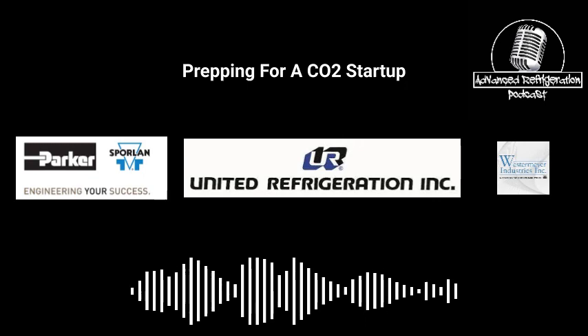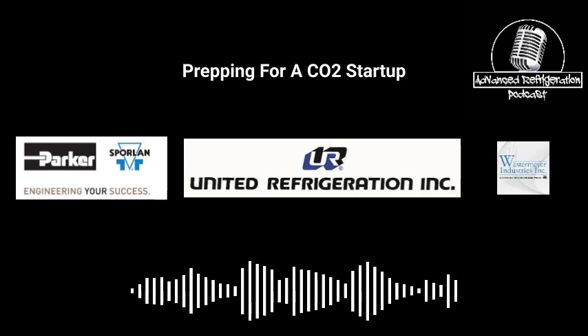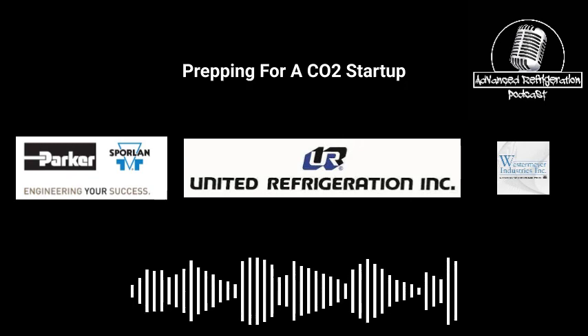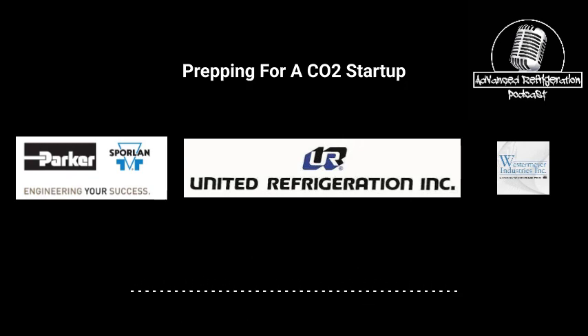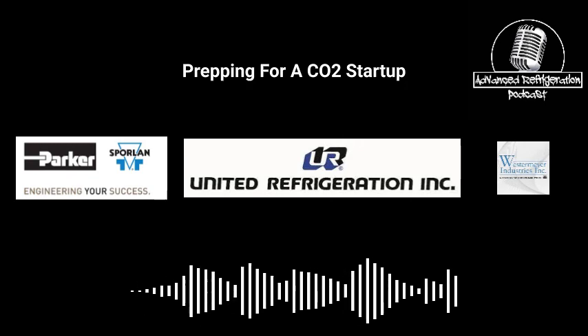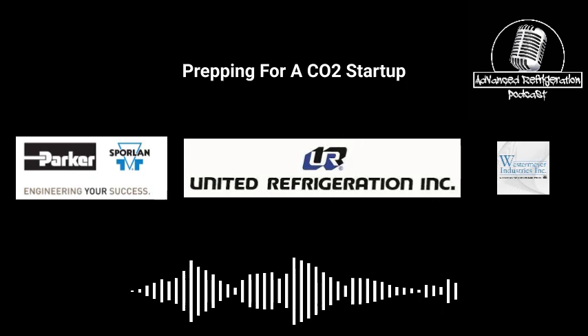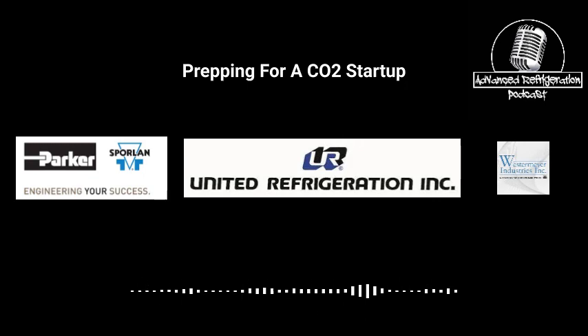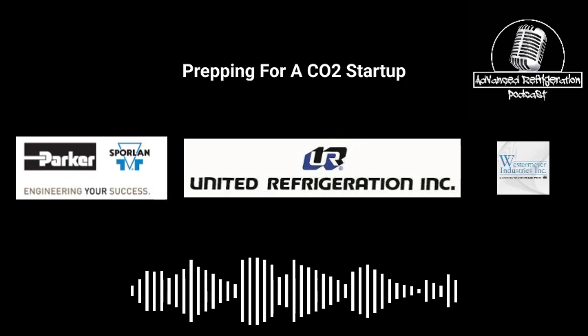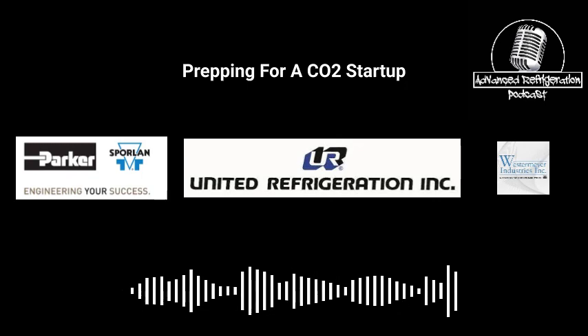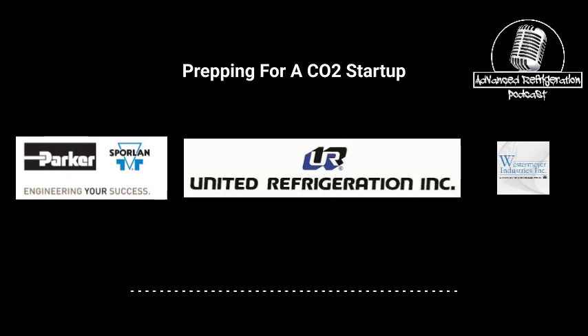The more time you spend making sure all the case controllers are good, the fewer problems you're going to have. Making sure sensors aren't flipped. That is the biggest thing I see: sensors that are bad, sensors that are flipped, and stuff that gets missed like the pulse valves tied to the lights, the pulse valves tied to the fans. The fans are the pulse valve output. Really? Oh yeah, it happens all the time.